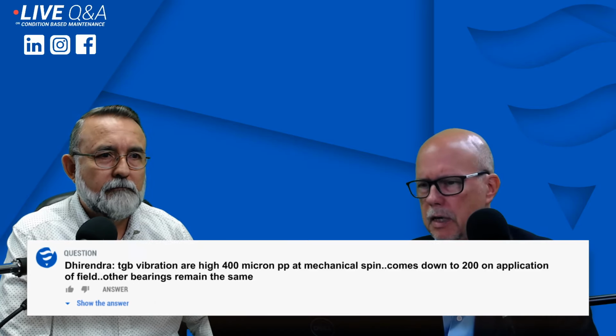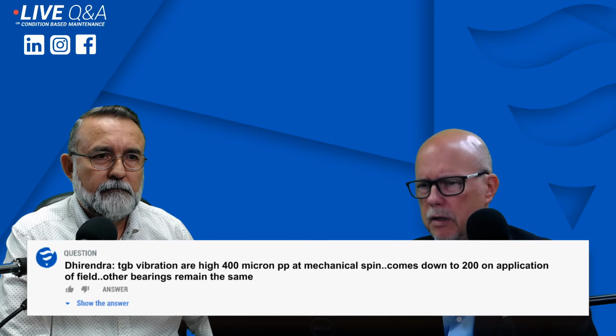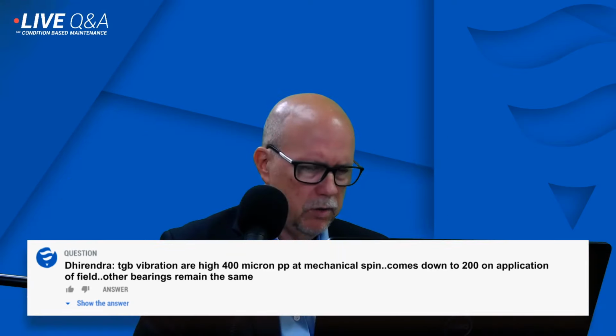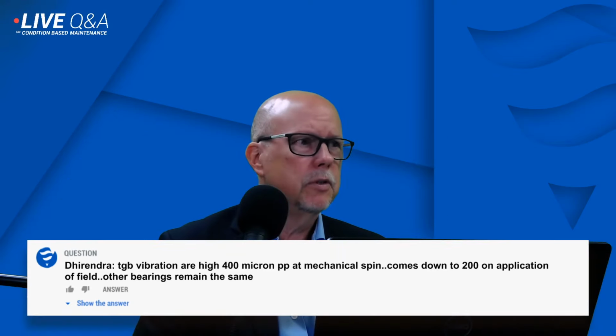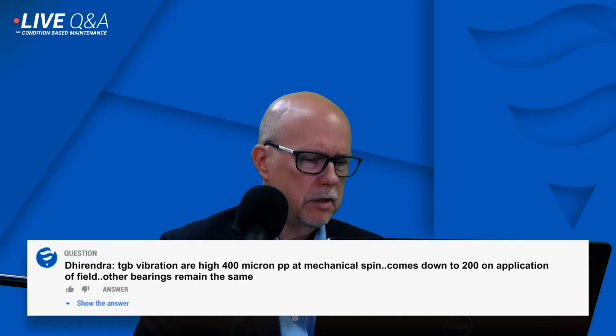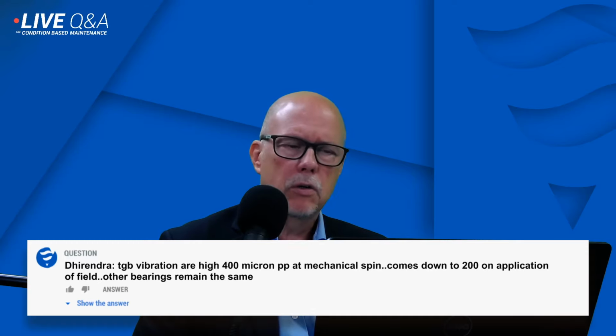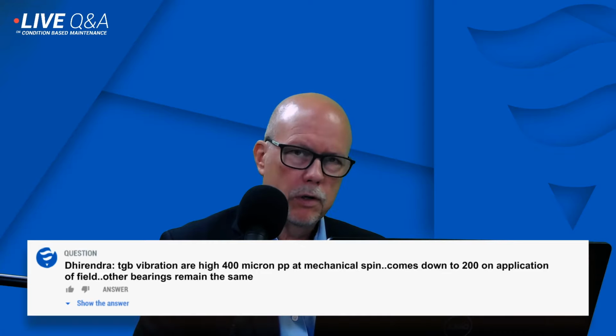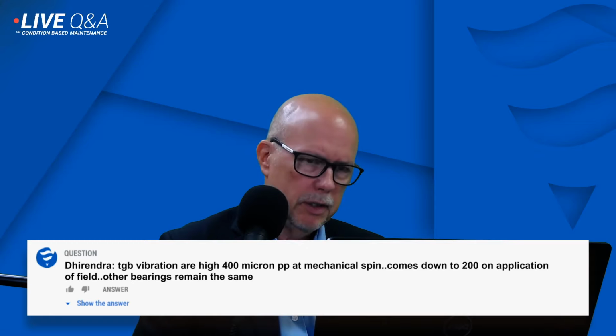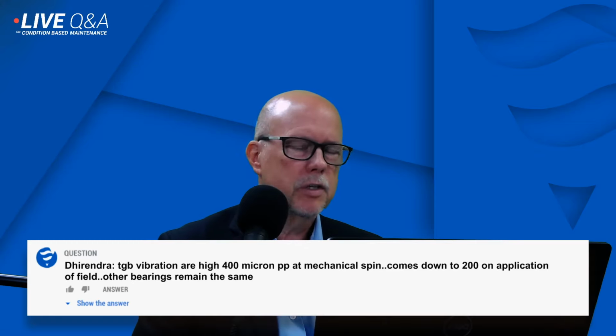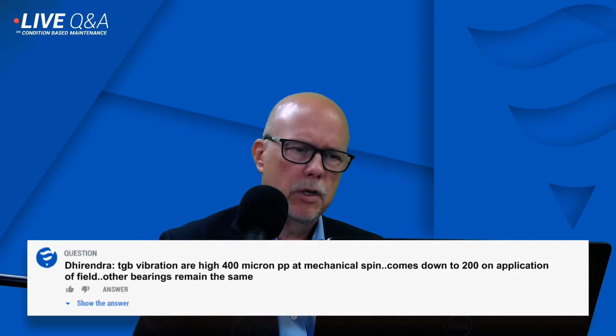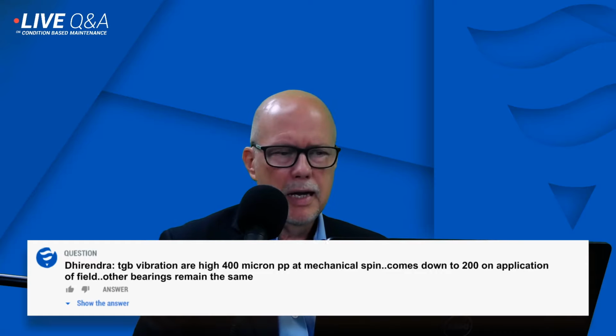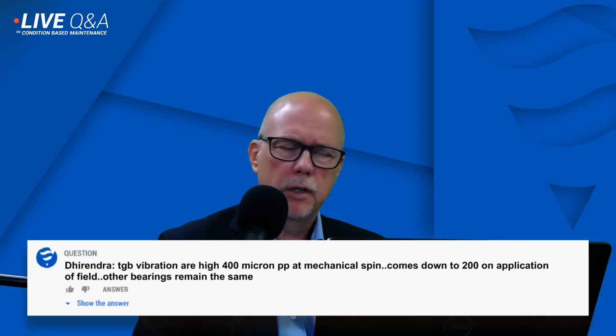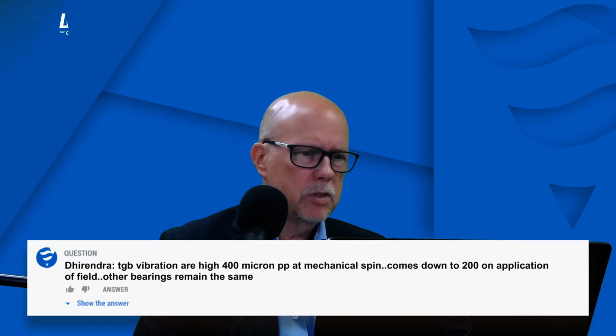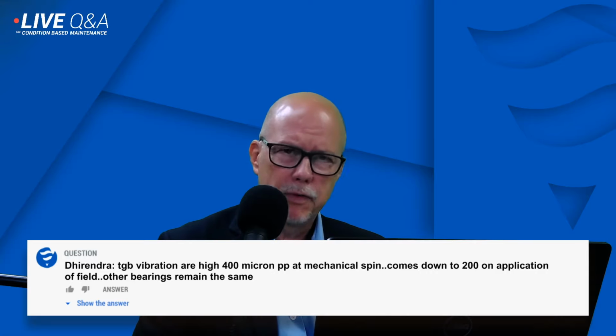Well, I would love to see more data on that unit. It is possible that when you apply the field, the axial position of the unit will change. In most cases, the rotors are installed slightly lower than the core, so that when you apply the field, the rotor is slightly lifted, giving the thrust guide bearing a break. Maybe the change in axial position of the whole unit has an impact on the effect of water in the turbine. But with little information, that would be my first guess.